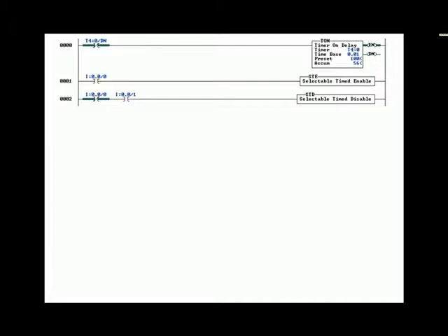Okay, in your lab, in ladder 2, I had you put the logic you see here, which is basically a free-running timer that is running with a time base of 1/100th of a second, 0.01, a preset of 100. Whenever the preset equals accumulate, which is 100, the timer's done, the run goes false for one scan, and the very next scan, it's reset, and it continues for another 100/100th of a second. So it's continually cycling with a preset of 0 through 100, 0 through 100, 0 through 100. This gives us a value in the accumulate register for T4:0 that's continually changing by 1/100th of a second for 100/100th of a second, then it resets and starts over again.